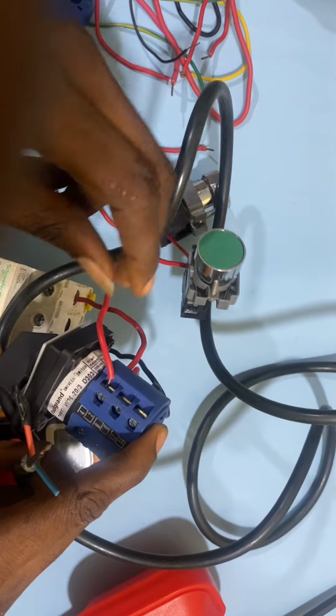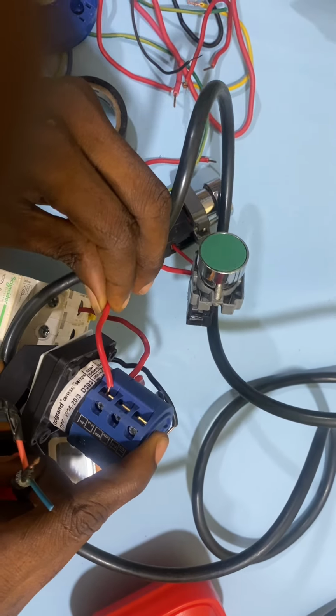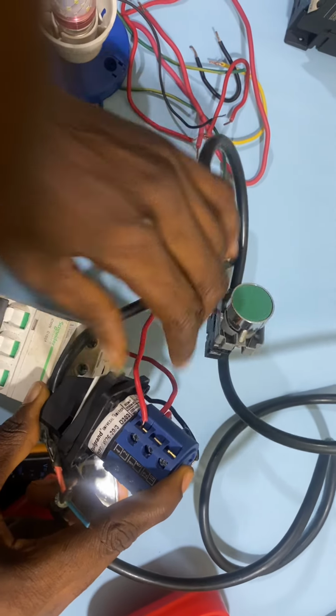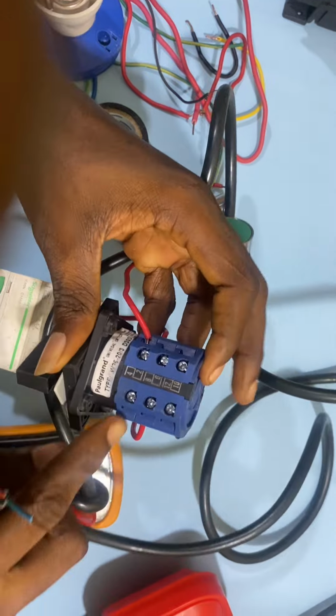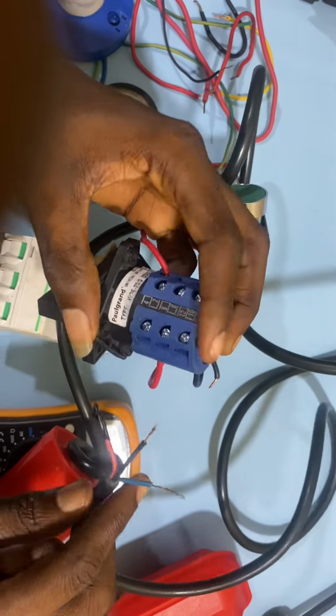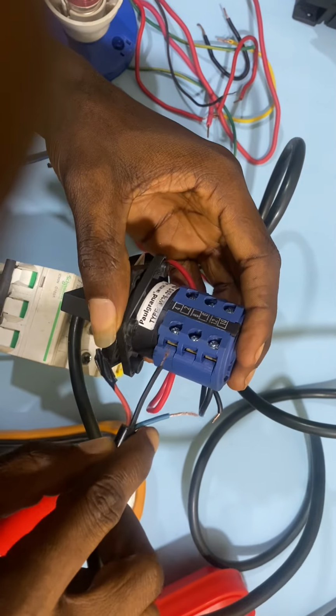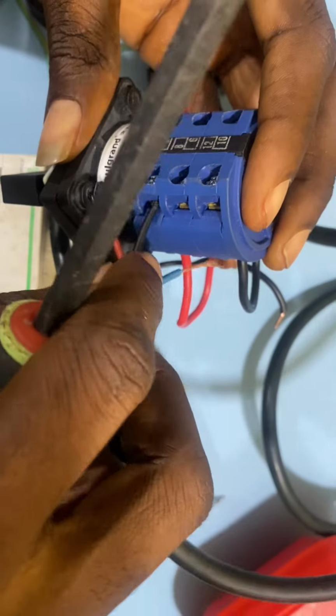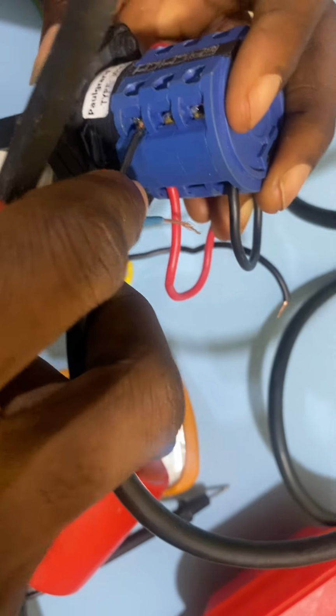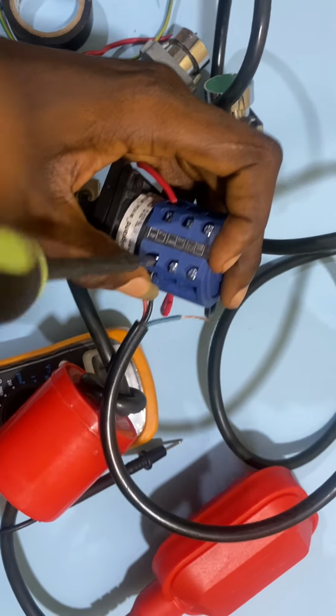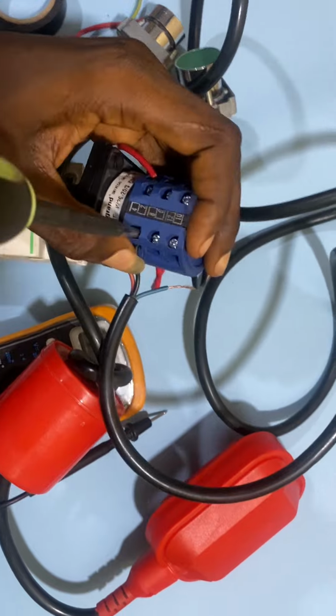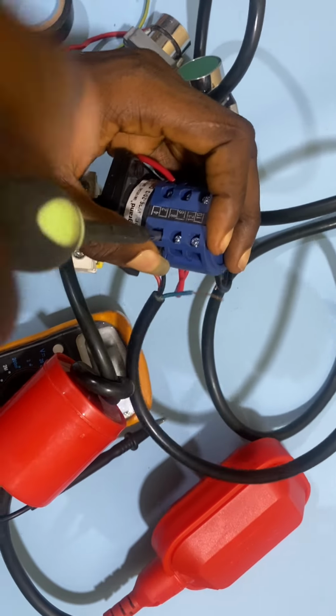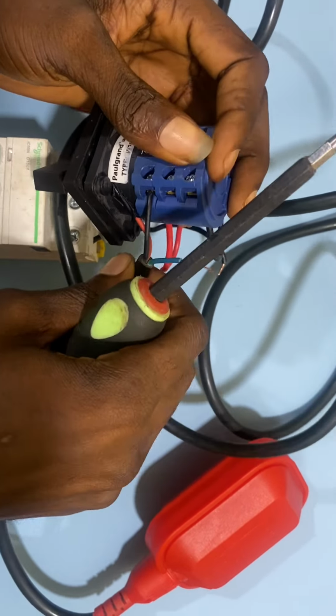Note that this phase, we take this phase to go to our start and stop button. So therefore it means that this phase output should go to our float switch. So I'm using this point now. So I'm connecting the float switch at this point. I'm going to slap it down also. All right, I'm done with that.